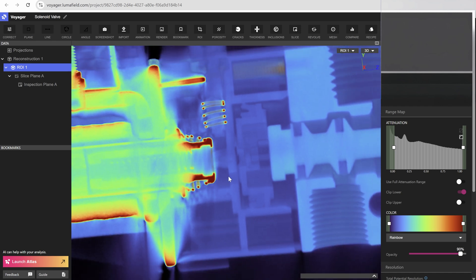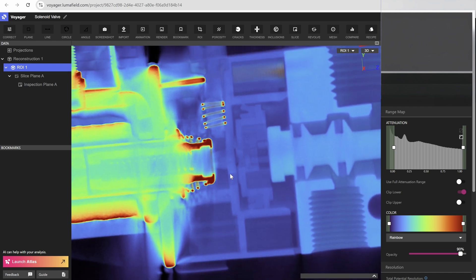Now this gallery here has a port heading right onto the head of this whole piston assembly that's pushing against the spool. So if the solenoid is able to fire, it will open up this port, pressurize this whole volume, and impinge on this piston. Piston head moves this way, spool moves this way, and the valve fires and opens.